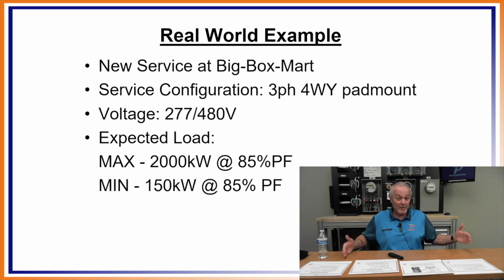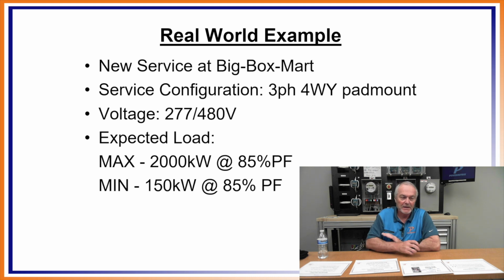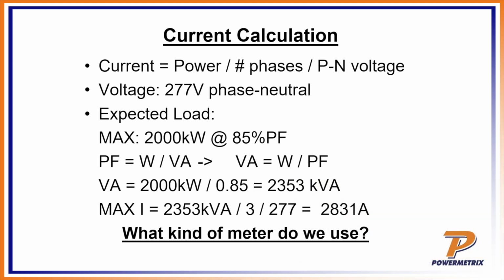So that we can know what meter we need to have and what CTs we need to have, right? The CT is definitely critical when we start talking about max and min, and we're talking about rating factors and extended ranges. Those are two critical things that we need to know to be able to size them correctly. Pick the right one. So current calculation, we need to know that current. You can take the power divided by the number of phases by the phase to neutral voltage.